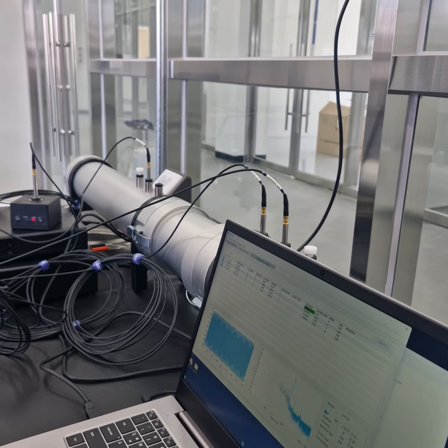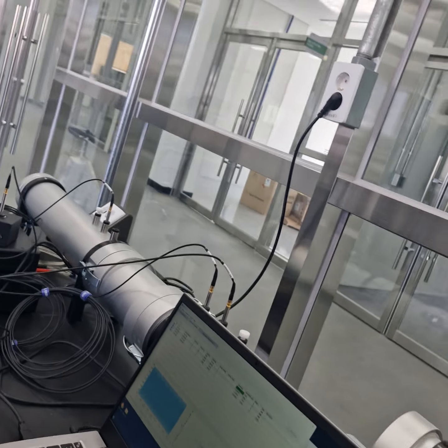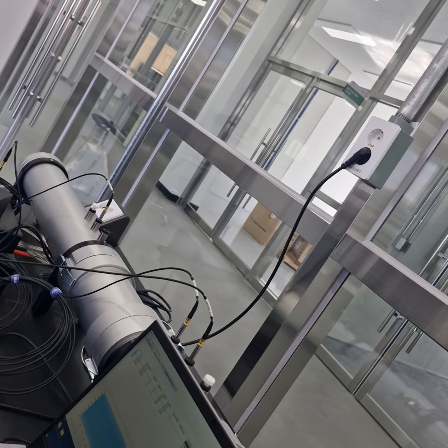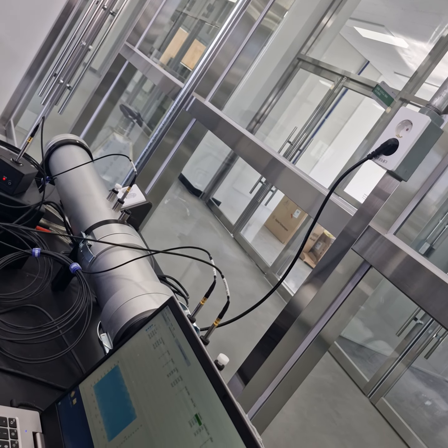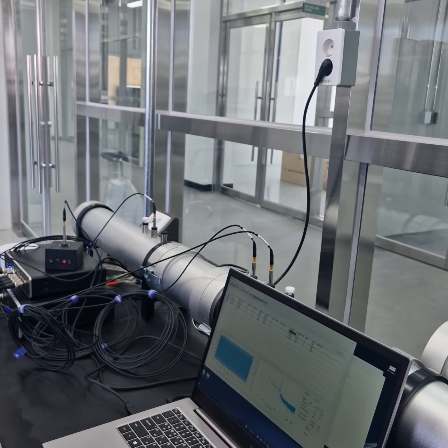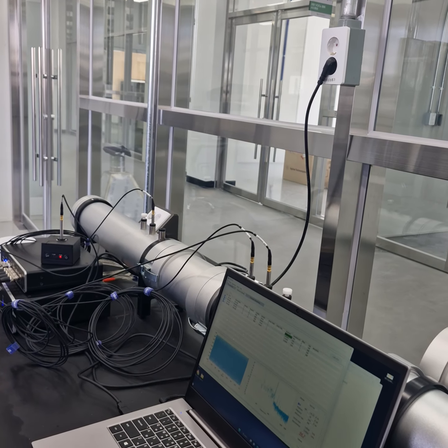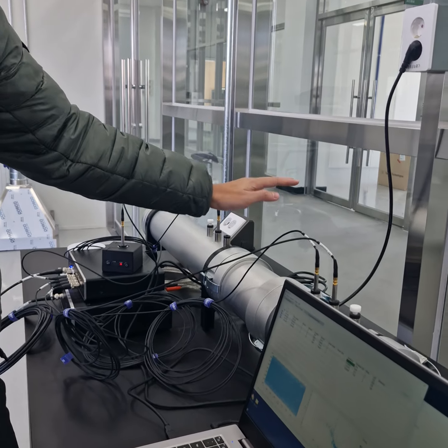Raymond, my boss has a question. In the case of transmission loss, why didn't you connect this one? We need to do the phase calibration first. In the transmission loss test, the sample is put in here, so we don't need this.